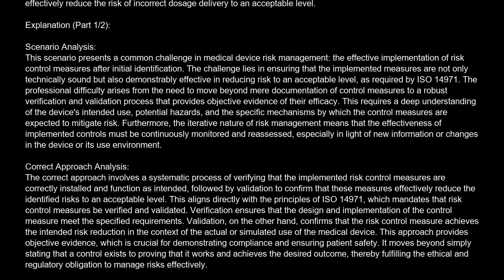Correct answer is C. Conduct objective verification and validation activities to demonstrate that the implemented risk control measures effectively reduce the risk of incorrect dosage delivery to an acceptable level. Explanation. Scenario analysis. This scenario presents a common challenge in medical device risk management: the effective implementation of risk control measures after initial identification.